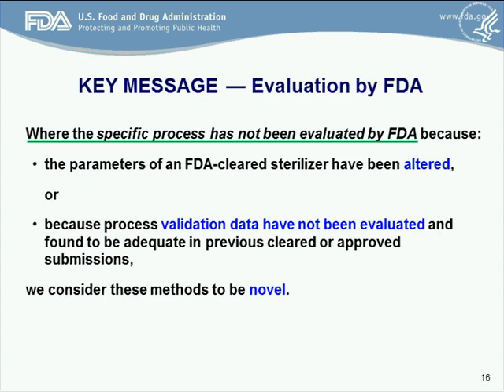This is the key message throughout the guidance document: evaluation by FDA of validation data. Where the specific process has not been evaluated by FDA — because the parameters of an FDA-cleared sterilizer had been altered, or because the validation data had just not been evaluated based on a particular submission — we consider these methods to be novel. We're looking for a high degree of assurance that each method has been adequately validated, whether that means conformity to standards or based on information we've already received. In the instance of novel sterilization methods, we're going to be looking at the validation data for the first time.